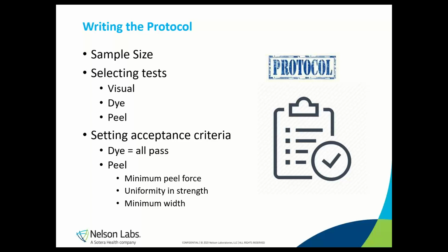For seal integrity, the preferred test is dye migration. This method is capable of detecting seal gaps as small as 50 microns. Since we're only looking at the seal in this validation, we want to use the more sensitive seal test. So dye migration is preferred over bubble.